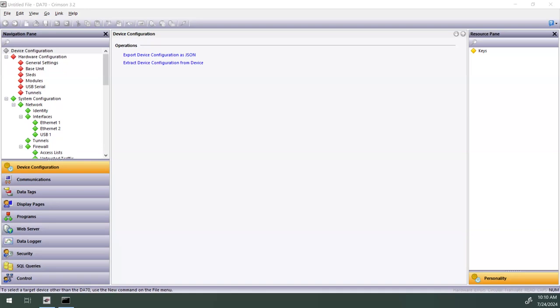Now, to illustrate this, I'll be connecting a Modbus RS485 environmental sensor to a FlexEdge DA70 on my test bench. This Modbus RS485 device is, of course, a serial connection, and we'll actually be reading temperature and humidity from that sensor and publishing that data to an MQTT broker.